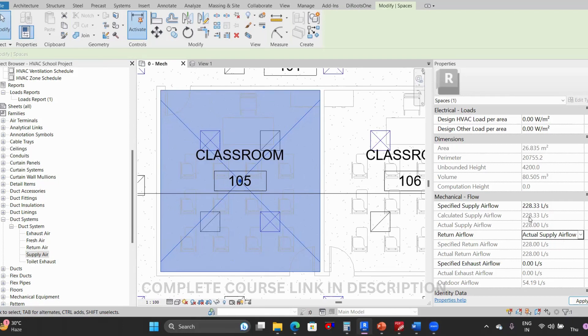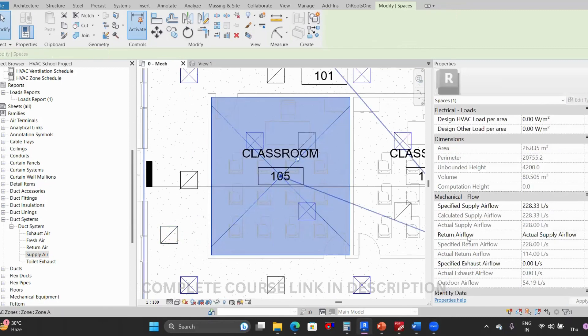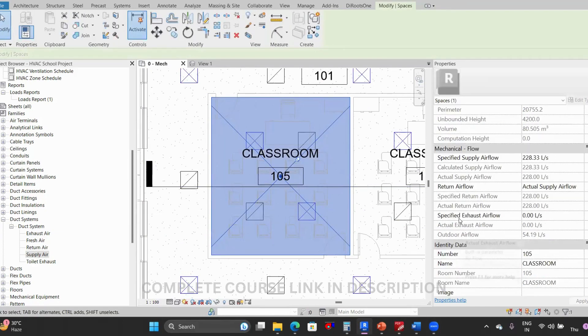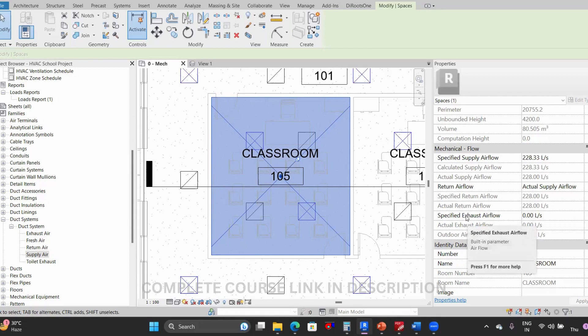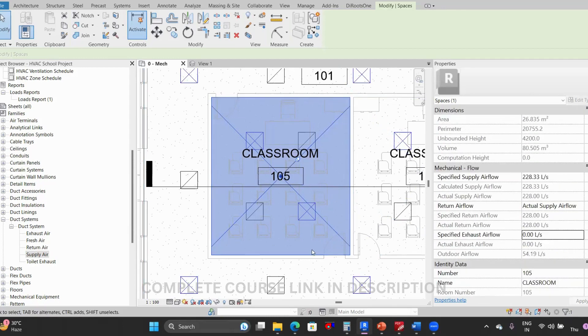If you want the return to match the calculated value, you can select calculated. The actual return air flow changes as per the diffusers placed in the model. For exhaust, there is no 'calculated exhaust' because Revit does not perform exhaust calculations. You can specify the exhaust value manually, and when you place an exhaust diffuser in the room it will show the actual exhaust air flow. Outdoor air flow is taken as per the space type defined earlier — for example, classroom settings.